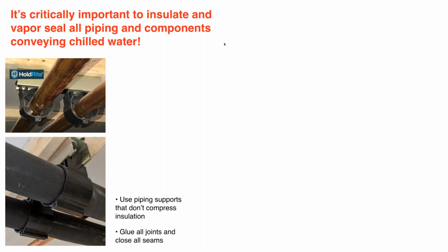If you've not done chill water cooling and you've done hydronic heating, you've probably put in systems where you don't worry about condensation on copper piping. If you take this copper piping and start running 45 or 50 degree water through it, literally within minutes there's going to be water droplets on the bottom of that tube dripping on whatever is below it, okay?